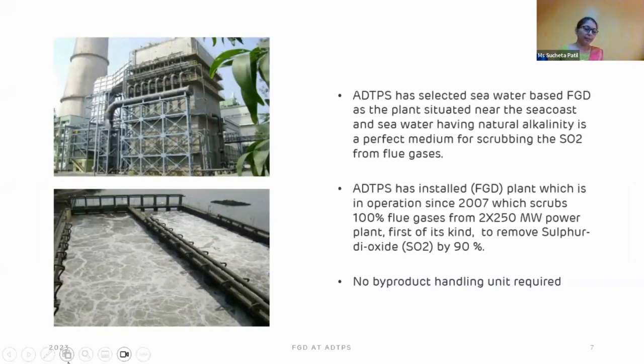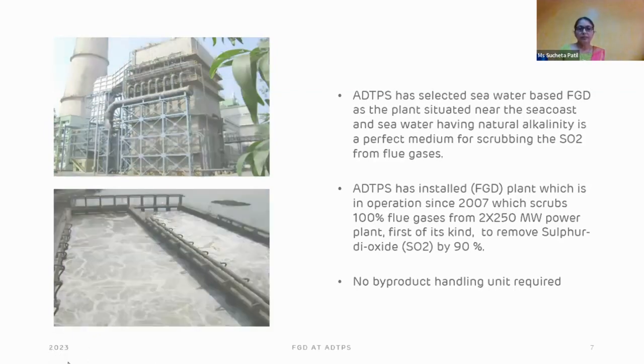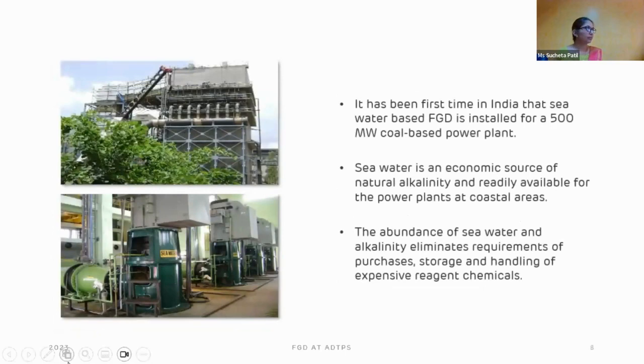We saw there are different types of methods for removing SO2, mainly classified as wet method and dry method. Looking at the merits and demerits of both types, at Dahanu Thermal Power Station we chose wet type FGD because it has more merits over the dry method. The FGD installed at Dahanu was the first time in India that a seawater based FGD was used, and it was installed for 500 megawatt of coal power based thermal power plant.